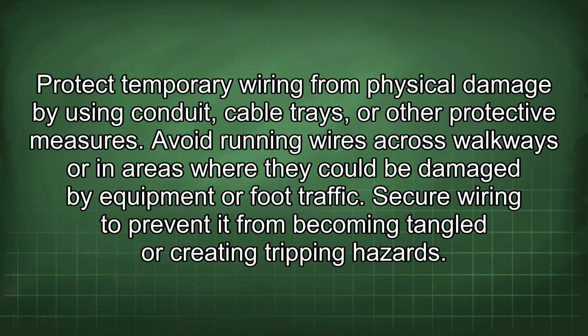Protect temporary wiring from physical damage by using conduit, cable trays, or other protective measures. Avoid running wires across walkways or in areas where they could be damaged by equipment or foot traffic. Secure wiring to prevent it from becoming tangled or creating tripping hazards.